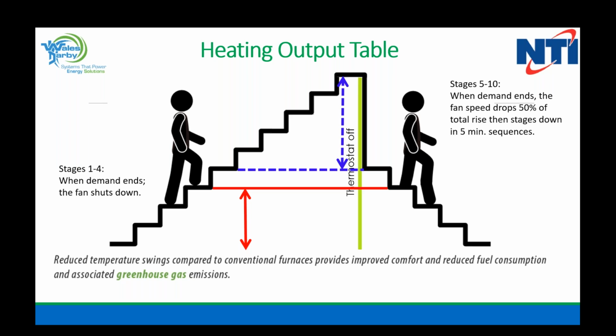And what we do is it will then remember where it was. So if it went to level 8, let's say, it will drop back down to level 4, and it will run there with the blower speed at level 4 for about 5 minutes. That way, if there's another demand that comes in, the blower will already be on. We'll start to deliver that heat, and we'll cut down on the amount of temperature that was lost within the space. And we'll keep it closer to that 70-degree line we saw on the last slide. That's what this system does. It has the ability to understand what's going on within the home and how to make that homeowner feel more comfortable within the space.